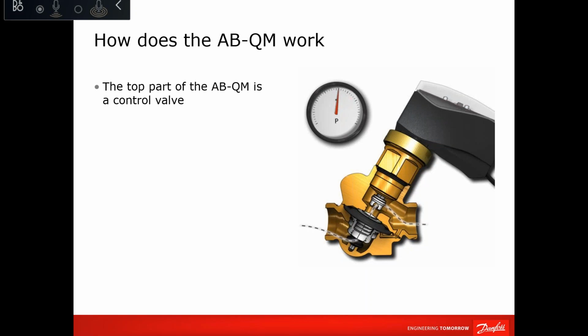Okay, and we have this question: what is the calculation for the DP location and how does it affect the pump control? Yes, this is, let's say, a service that Danfoss is doing. It is for your reference. It's not something that we are dictating.